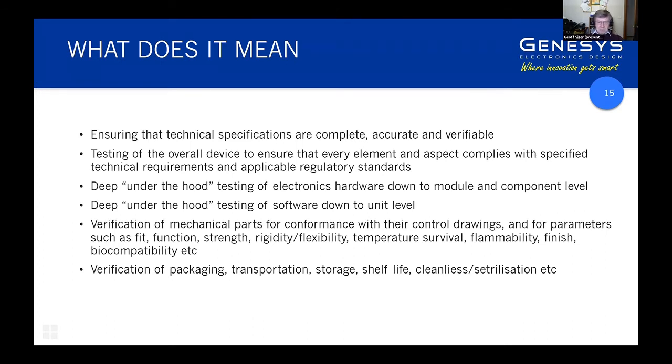I've seen statements that say the overall system shall meet a certain requirement, where that's dependent upon a whole heap of elements of the system, and that's in a specification for one particular element. So you can't verify the overall system compliance by looking at the verification for one particular element. You need to be really careful with those sorts of vague or imprecise specification statements that you can't verify.